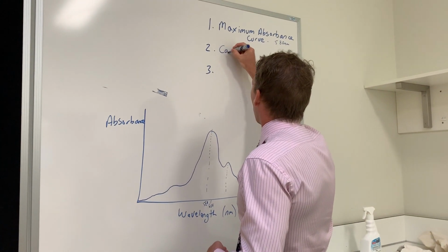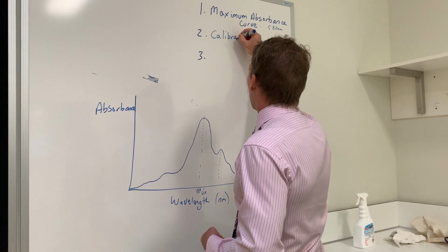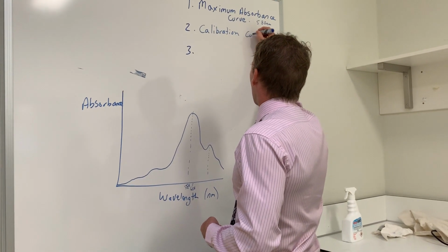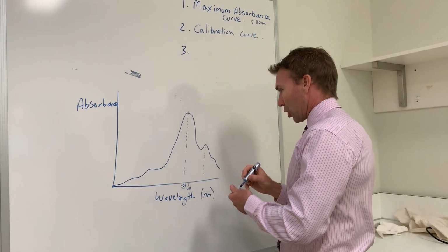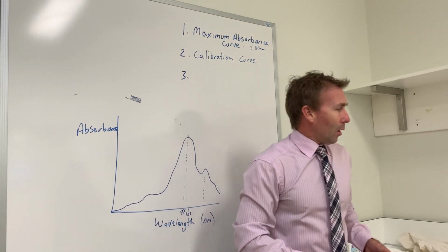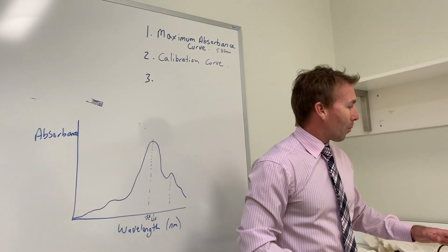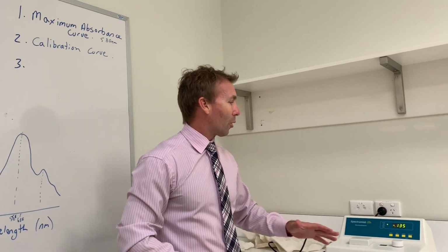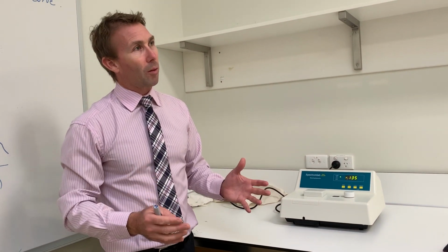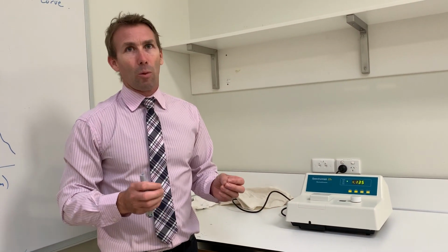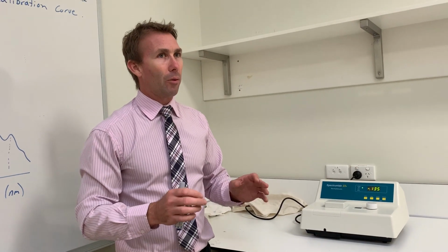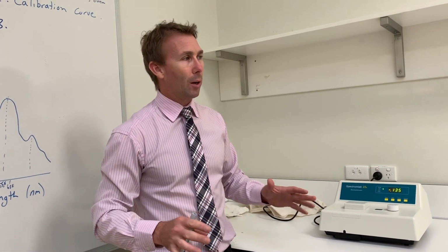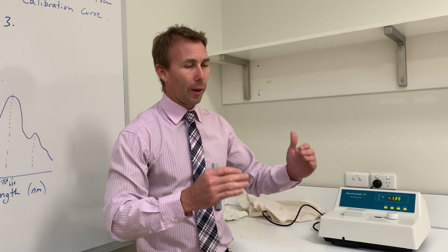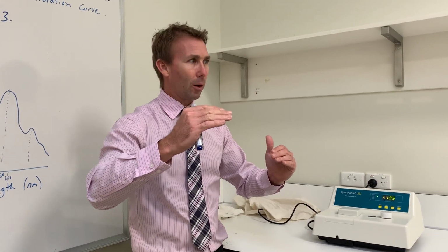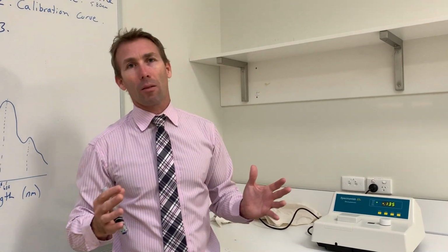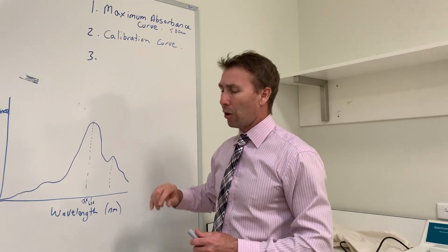Stage 2. You want a calibration curve. Now, the purpose of the calibration curve, you'll notice here on this screen, the only value you get is absorbance. Now, every now and again, people will do an IA and they'll have no way of knowing what the true concentration is. So what they'll do is they'll just compare the relative absorbances. And if that's the case, it's okay. You won't have a calibration curve.